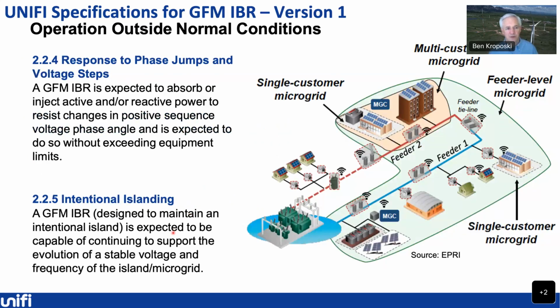And then continuing with this operation outside of normal conditions, you may have things like response to phase jumps and voltage steps that you would see on the grid. We want to make sure these grid forming inverters have the ability to either absorb or inject active and reactive power to resist those changes that are happening very quickly on the grid.